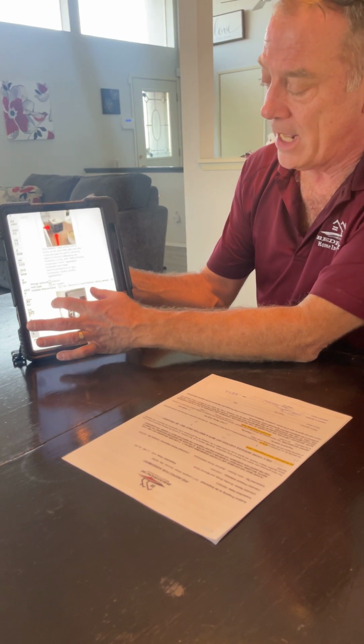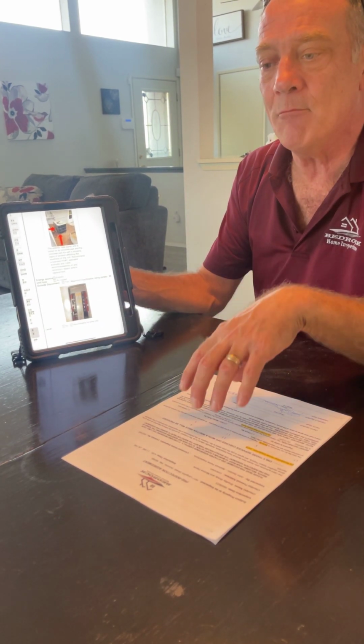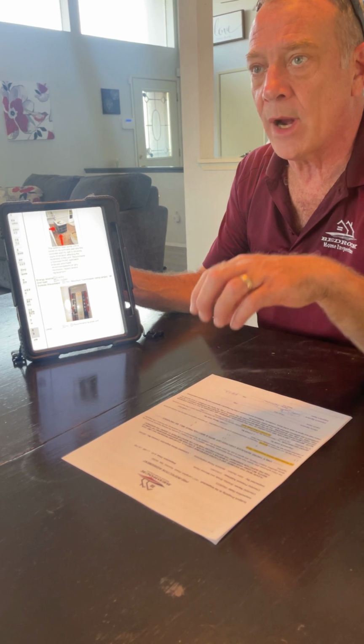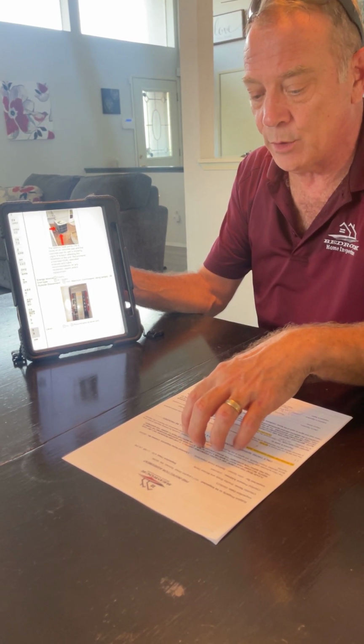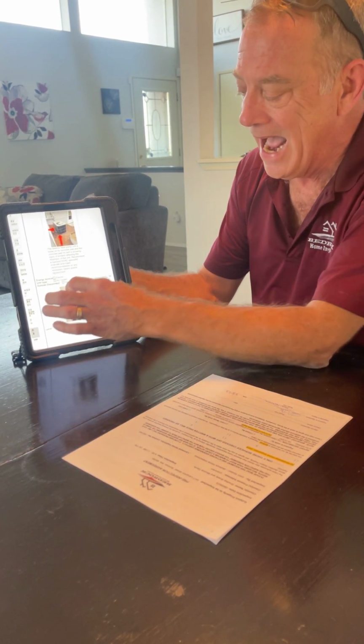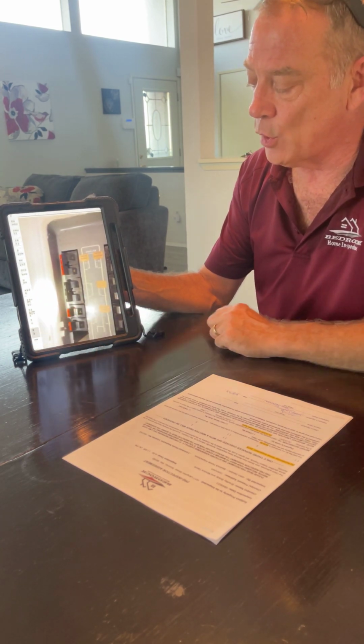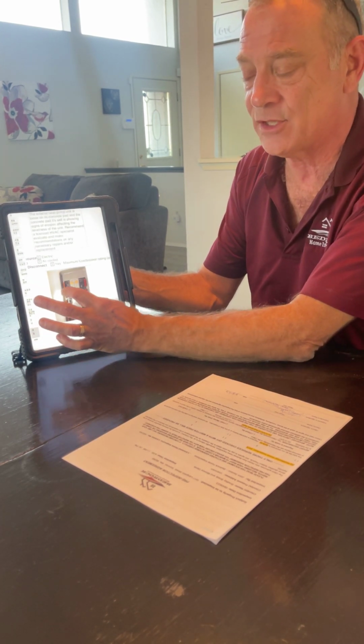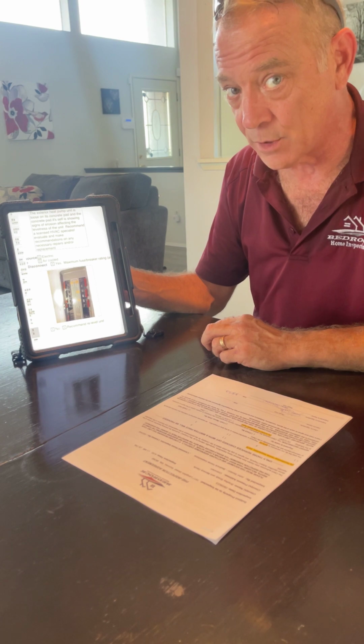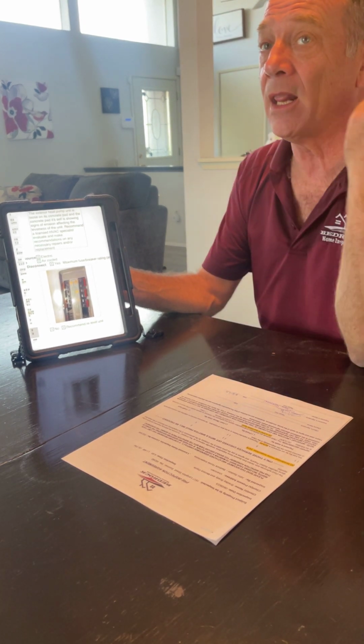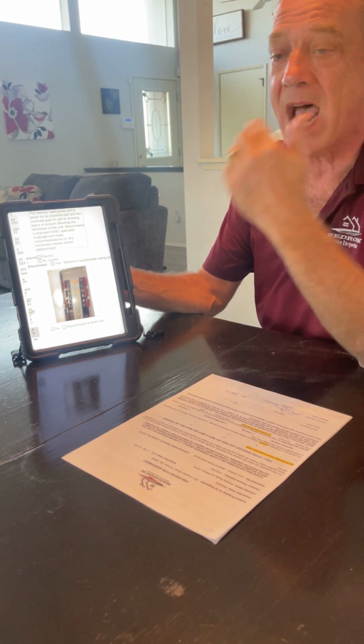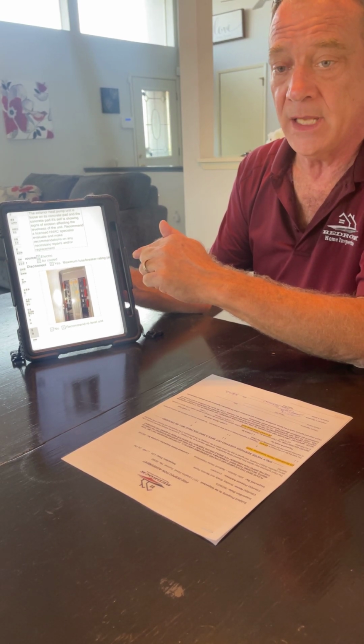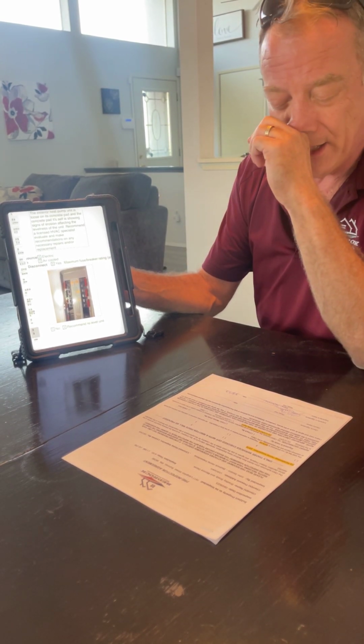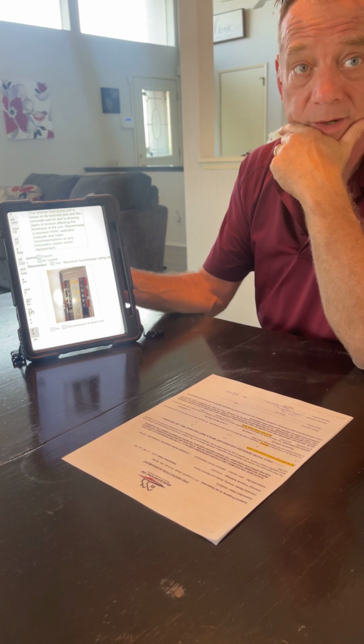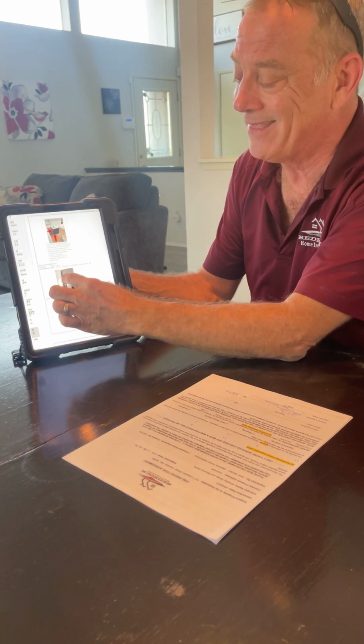The other issue is that the maximum circuit breaker for that heat pump unit should be a 30 amp circuit, but I believe in your electrical panel they installed a 50 amp circuit. That means if there's an electrical issue, it's not going to trip the breaker—it's going to start melting wires instead. So we need to get that looked at.